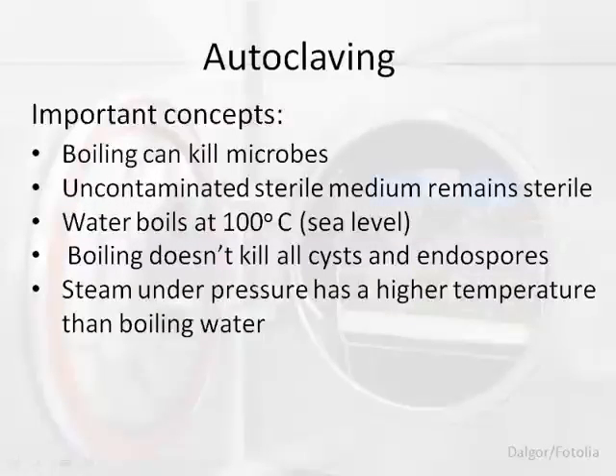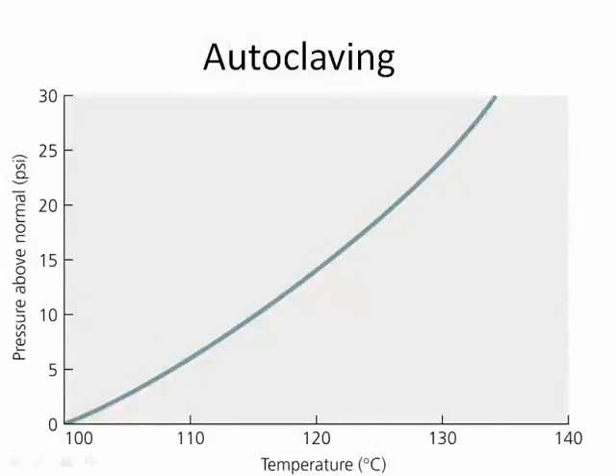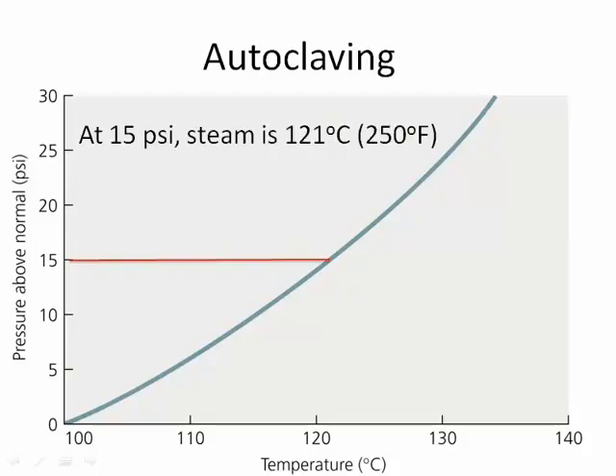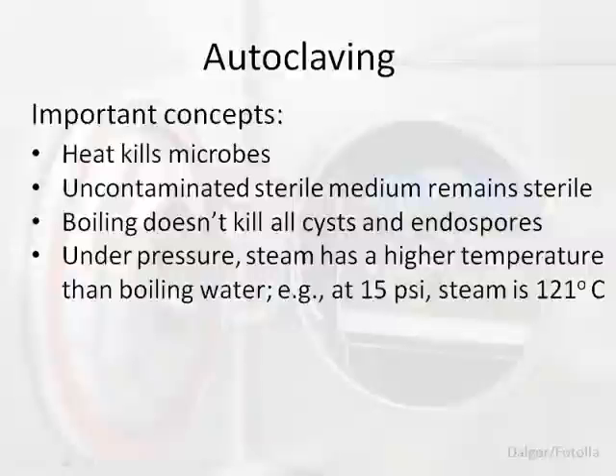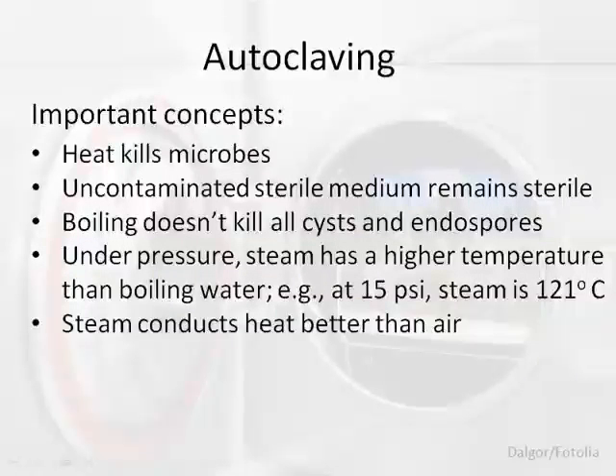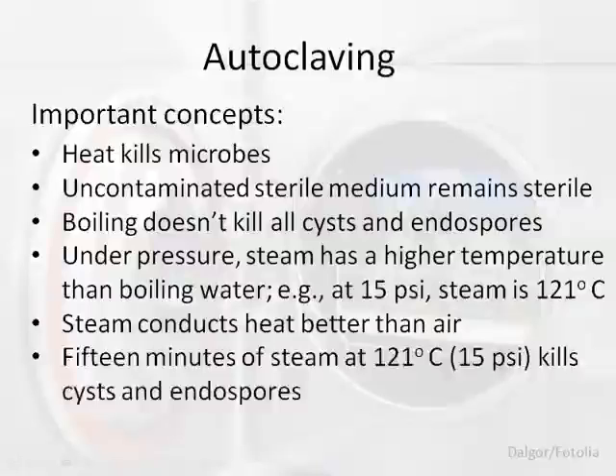Steam, under pressure, has a higher temperature than that of boiling water. The higher the pressure, the higher the temperature. For example, water boils at 100 degrees Celsius at sea level, but at a pressure of 15 pounds per square inch, the temperature for boiling must rise to 121 degrees Celsius. Steam has another advantage when we need to sterilize something. Steam conducts heat better than air. The result is that 15 minutes of steam at 121 degrees Celsius kills protozoan cysts and bacterial endospores.